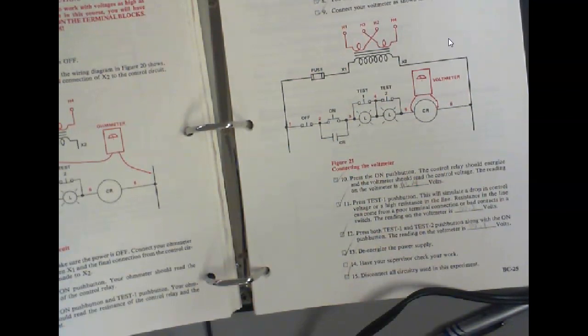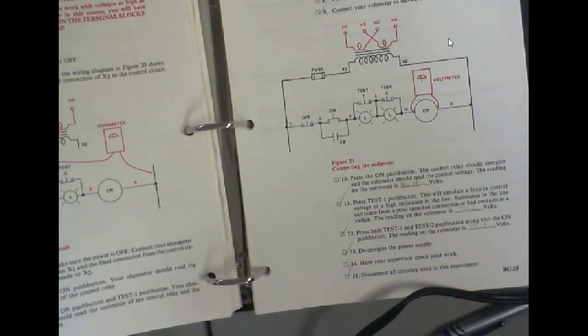We'll see if we got both of them in, odds are we can press the start button all day long and it won't energize. But once it's energized and I press both those buttons, sometimes it drops out and sometimes it don't. Because it all depends on the relay, right? You understand that? So this is going to be troubleshooting.